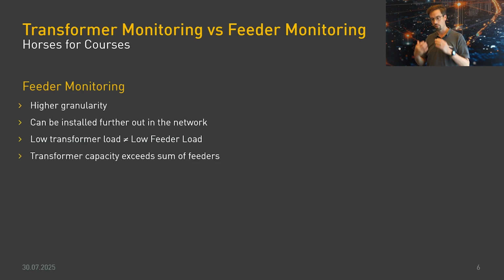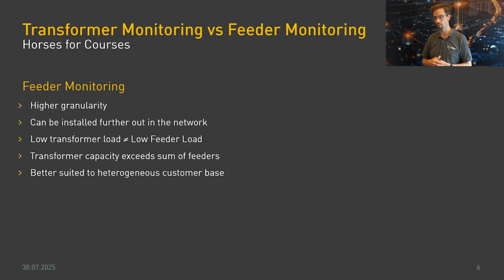Another way of looking at it is where the transformer capacity exceeds the sum of the feeders, it actually is not interesting to monitor the transformer, i.e. if I know the transformer's overloaded, it's way too late. If the load that's sitting on the feeders is more important, you have to start measuring them. And the kind of situation where that might happen is that you might have built the transformer well in advance of what you expect to happen, but the individual feeders may be overloaded already, and therefore you need to monitor those feeders as the first point of contact.